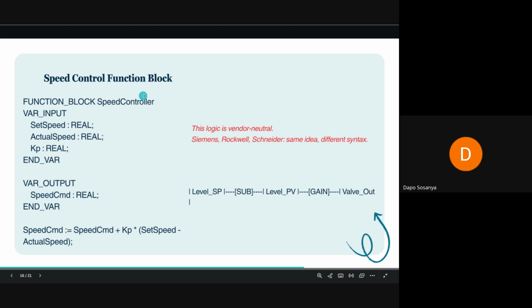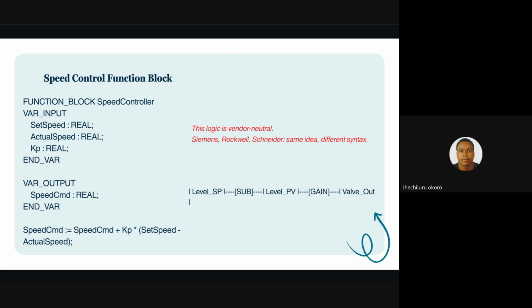Yes. Okay, so everything written here resides in the controller, the PLC or whatever - all of this code is translated into code and resides in the controller. The controller will start from line 1 of your code and run to line maybe 100. The time it takes the controller to run through all of those is the scan time.